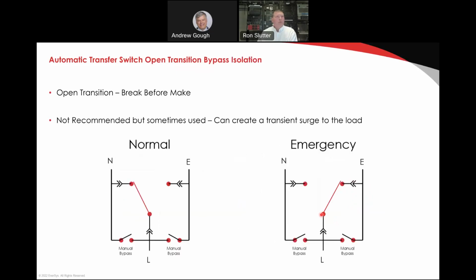All right, so as we move on, now we're going to get into a completely different kind of ATS, and this is called bypass isolation. So this is an ATS in open transition. So it's an open transition ATS with bypass isolation. So what does bypass isolation give us? It gives us the ability to manually transition without the automatic feature working. So this is something that a person has to do. So obviously, if you're in this mode, the automatic feature is not working.